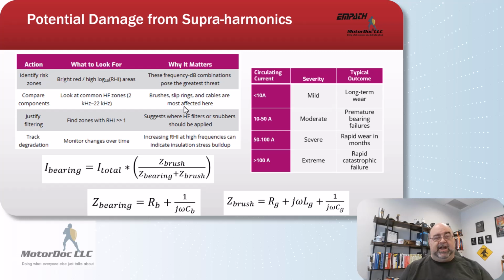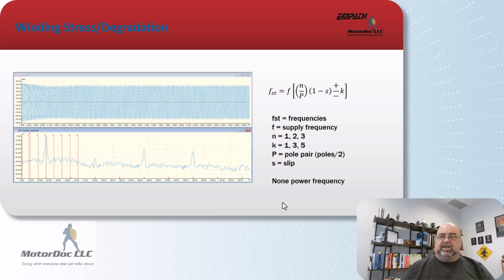In the meantime, as I approach the higher frequency, my bearing becomes, here's the formula, less resistive to current flow, it's the impedance, and my brush becomes a greater impedance, or is more resistant to current flow. And so as we increase the frequency, we start to have problems. The other thing is, when we start seeing these higher frequencies, we will start seeing winding stress.